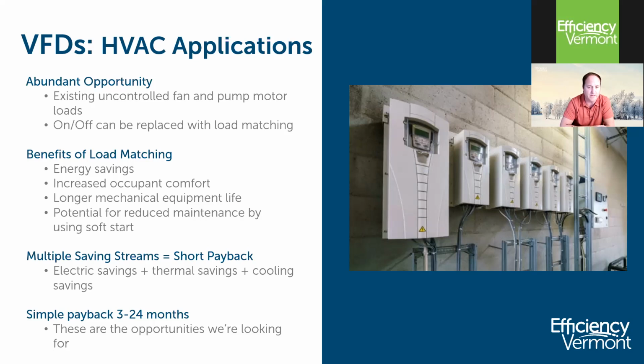You give some life back to the equipment, whatever that may be, an air handler, a rooftop unit, a pump. So multiple saving streams. This is probably most prevalent in exhaust fans. I do a lot of work in the ski industry. There's a lot of big kitchen hoods, 20, 30, 40 foot long, with lots of equipment under them. The hoods are sized for everything under that hood to run simultaneously, and that's rarely the case, especially midweek at a ski area. They're making a few burgers for the midweek staff, but the fan has 1 or 2 speeds. Most of the time it has 1 speed, so it's on full tilt.